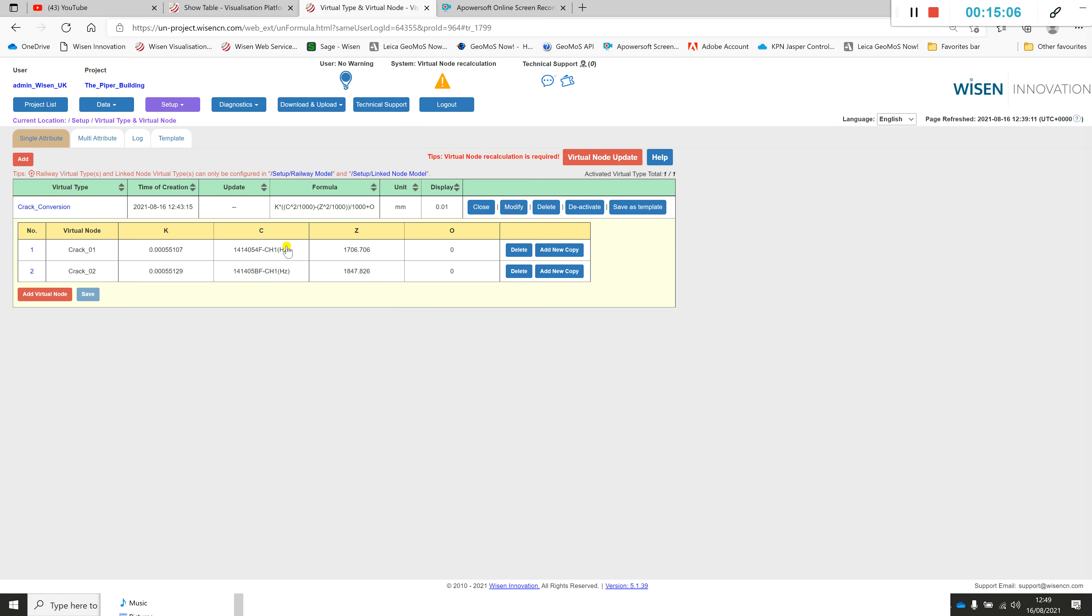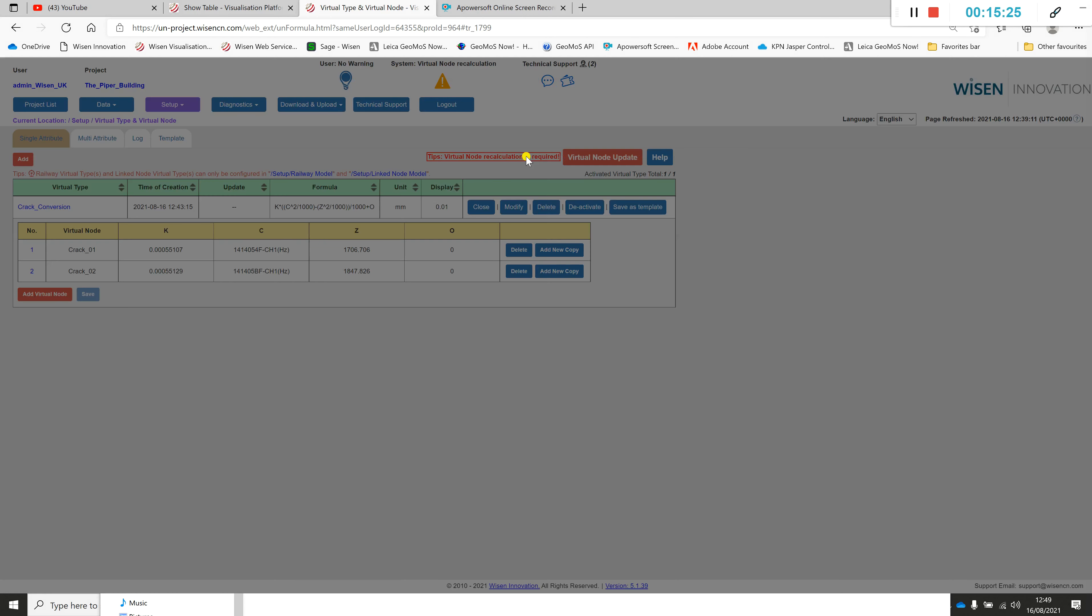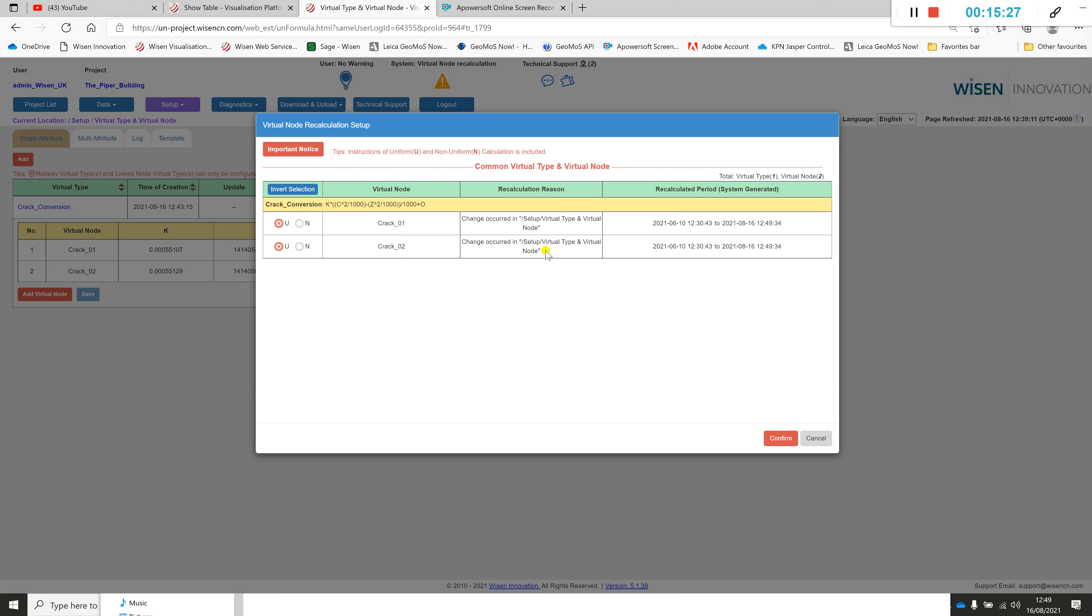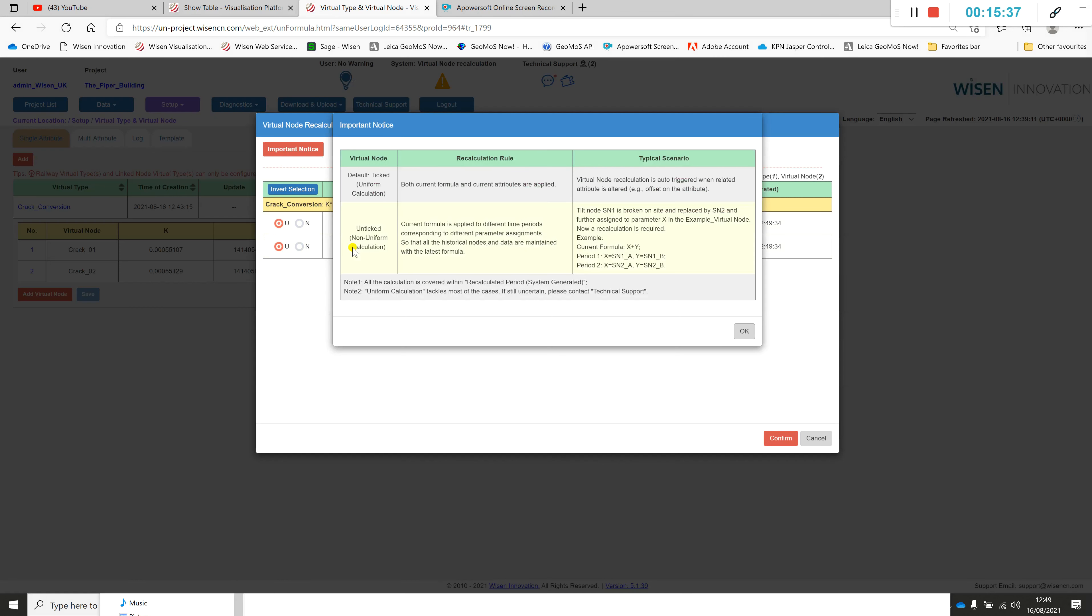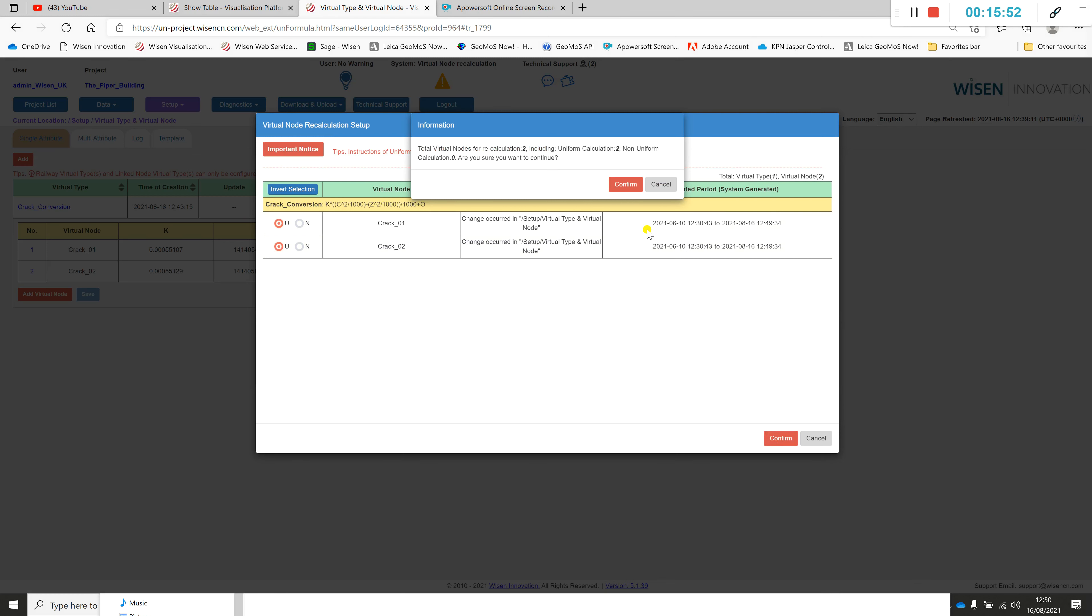You've got a little bit of flashing text here now. Essentially this is a summary page. You've created the formula, you've associated the sensors, and now it's asking you to do the virtual node recalculation. You might have done this a week after the event after installation. You're basically recalculating that historical data and then applying that formula going forward. So we click this button, the flashing button. It's a uniform calculation. The most common variant will be the uniform calculation. Click confirm.